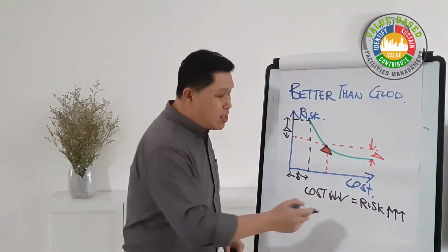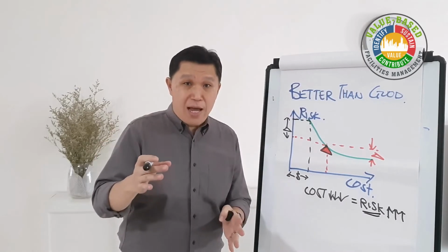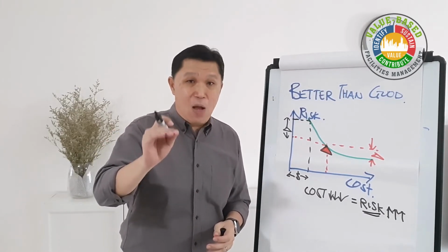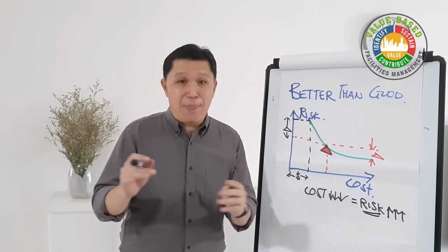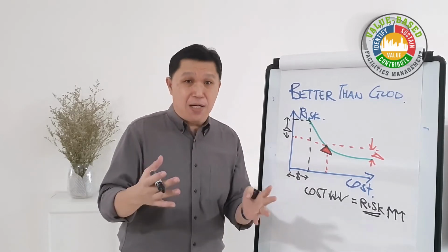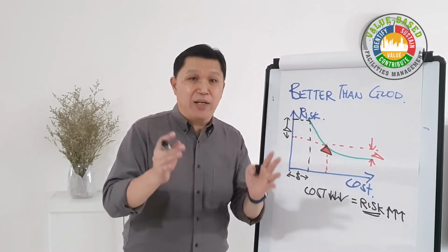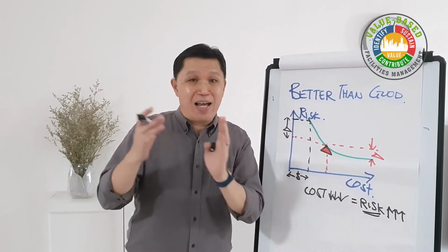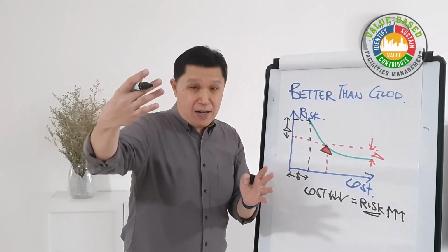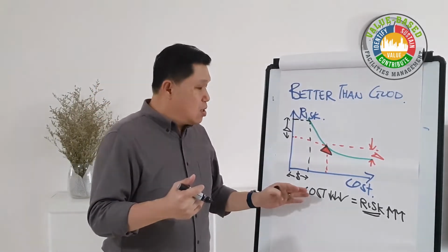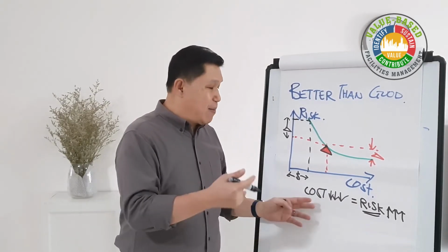What I mean by the risk here is that if the chlorine is overdosed, over time it may cause pitting. And when pitting occurs on the heat exchanger, what may be the consequence? For example, the chiller has to be shut for repair work, and as such, it may create a risk whereby there may not be a standby chiller for the operations. So how may we think of an alternate solution? How can it be better than before?